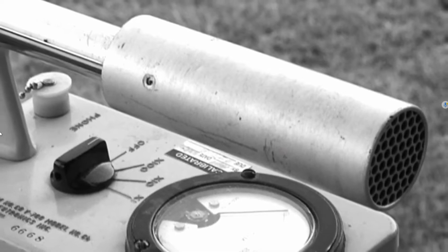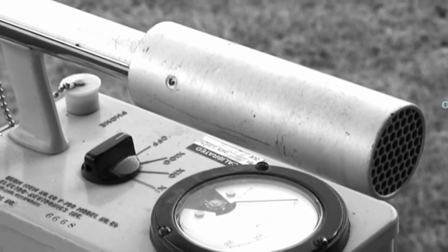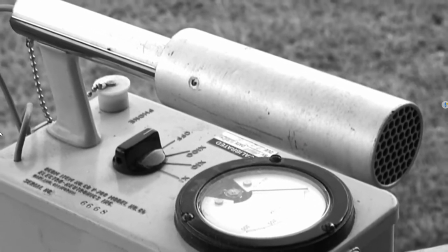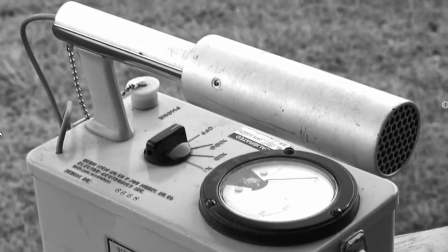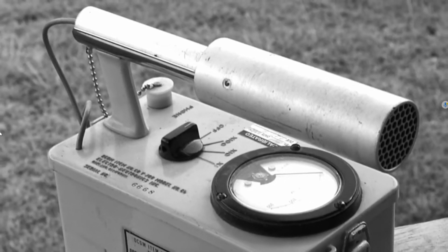So inside every Geiger counter there is one or more Geiger tubes. The tube has a wire going down the middle and a metal can around the outside and a special mixture of gases. So ionizing radiation comes along, it has to get through the metal and it will ionize some of the gas. There is a huge voltage difference between the wire and the can, which means that if there's any charge in the air, it'll get moved very strongly. The electrons get pulled down to the wire and the positive ions get pushed out to the can. It's a very, very strong electric field.